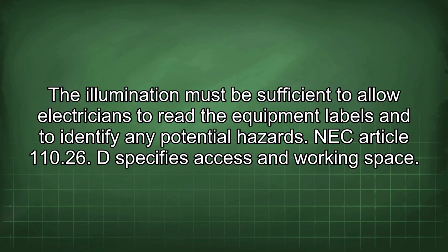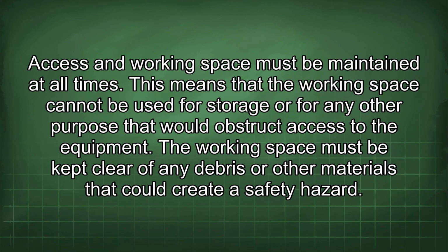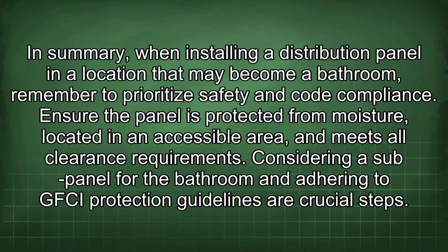NEC Article 110.26 D specifies access and working space. Access and working space must be maintained at all times. This means that the working space cannot be used for storage or for any other purpose that would obstruct access to the equipment. The working space must be kept clear of any debris or other materials that could create a safety hazard.